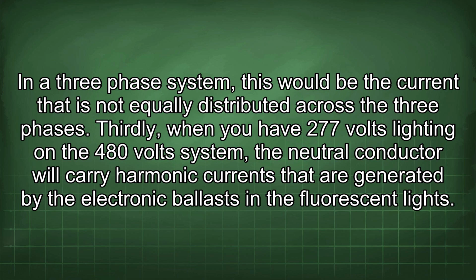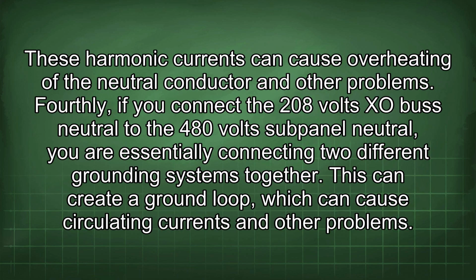Thirdly, when you have 277 volts lighting on the 480 volts system, the neutral conductor will carry harmonic currents that are generated by the electronic ballasts in the fluorescent lights. These harmonic currents can cause overheating of the neutral conductor and other problems. Fourthly, if you connect the 208 volts XO bus neutral to the 480 volts subpanel neutral, you are essentially connecting two different grounding systems together. This can create a ground loop, which can cause circulating currents and other problems.